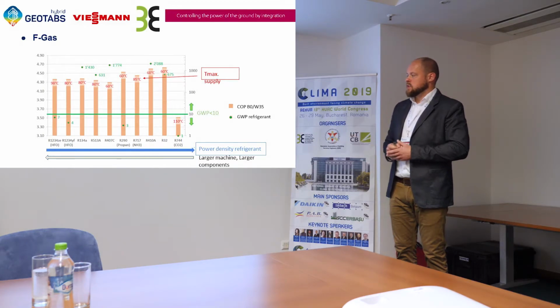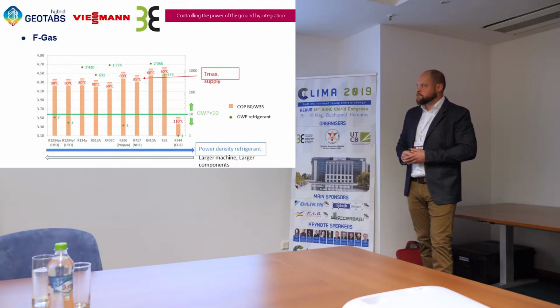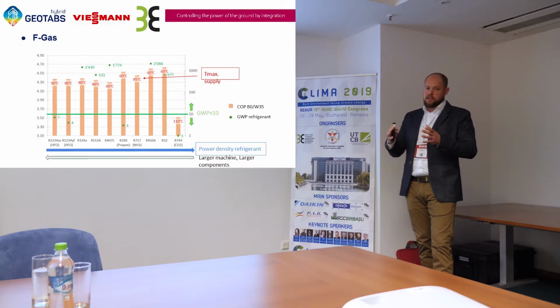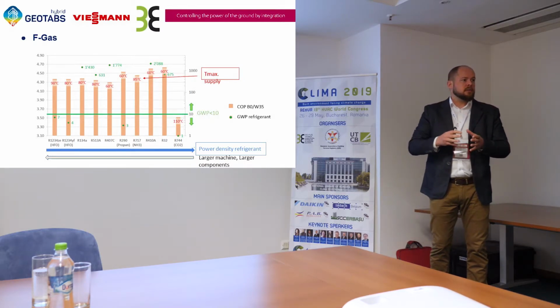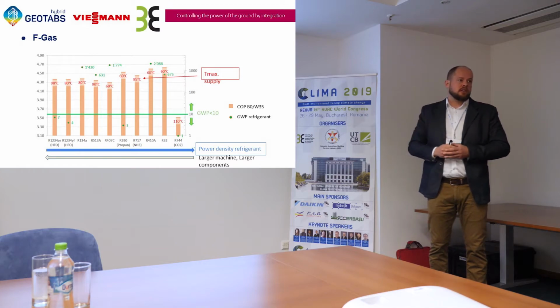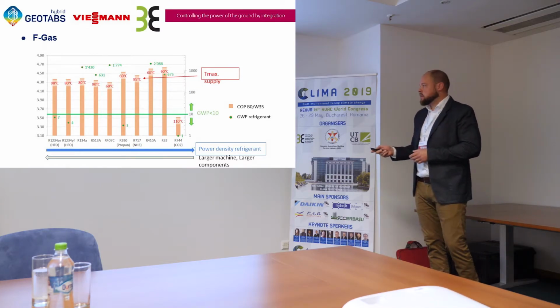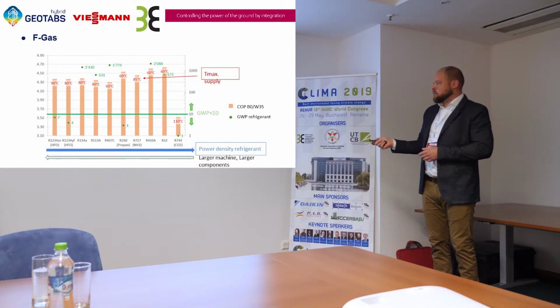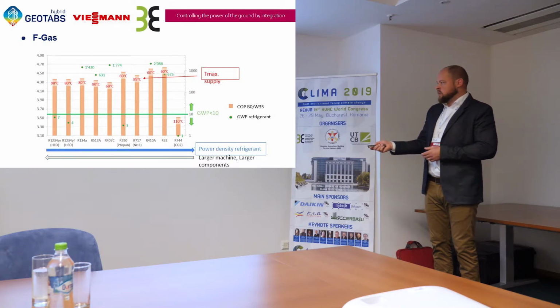That's really interesting. If you look at buildings where we want to make domestic hot water locally in each apartment, you have to have the option of a higher departing temperature. So in the future, we have to be below the GWP of 10. That's very important. So you see only propane is ready now, and the two newer refrigerants here are ready. This arrow indicates the power density of the refrigerant. That means that we go higher when we go in this direction.